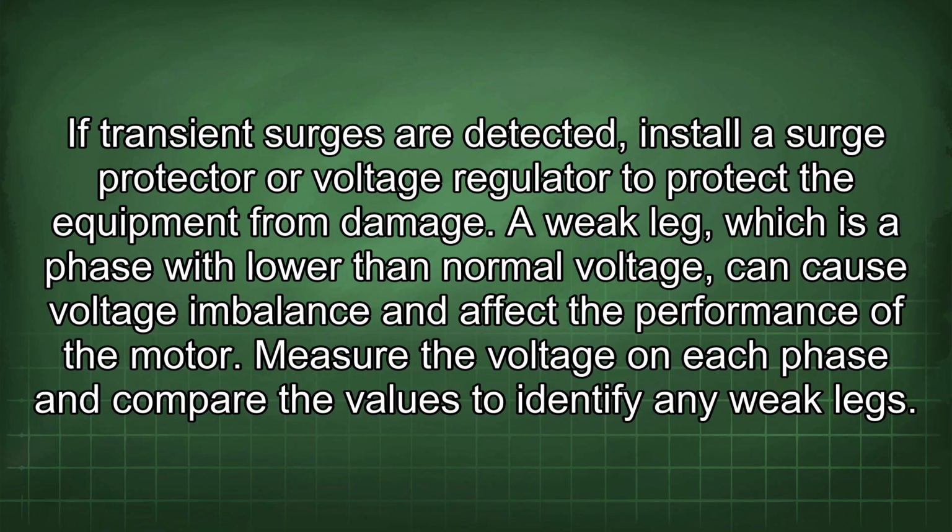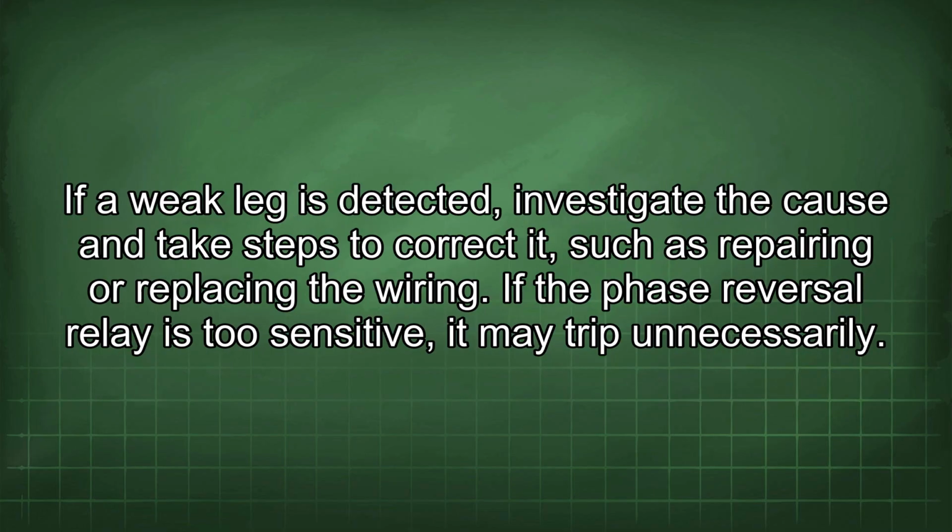from damage. A weak leg, which is a phase with lower than normal voltage, can cause voltage imbalance and affect the performance of the motor. Measure the voltage on each phase and compare the values to identify any weak legs. If a weak leg is detected, investigate the cause and take steps to correct it, such as repairing or replacing the wiring. If the phase reversal relay is too sensitive, it may trip unnecessarily.